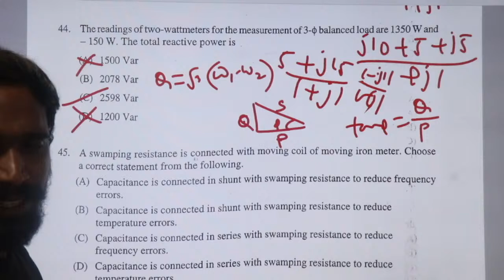From that, root 3 times W1 minus W2: 1350 minus of minus 150 equals 1500. 1500 multiplied with 1.732. Which is the correct answer? Nearly 2 times, not 200%, but 173%. We can calculate, but even so we can get the answer directly. Very good, Sharath, very good.